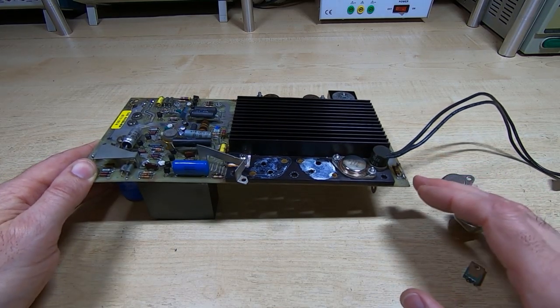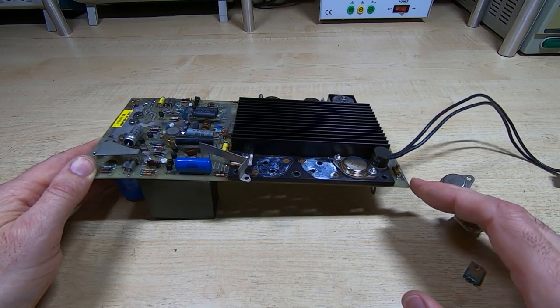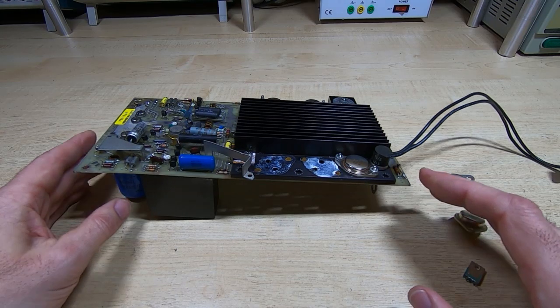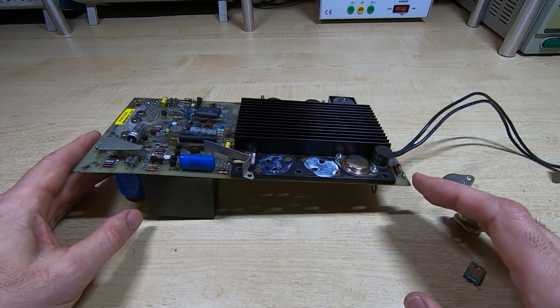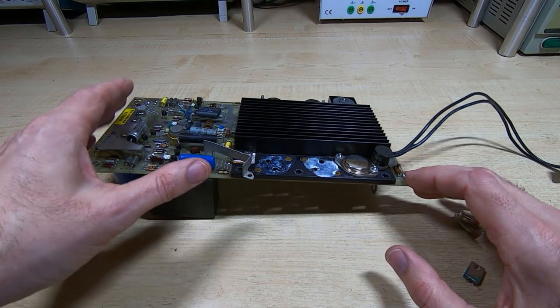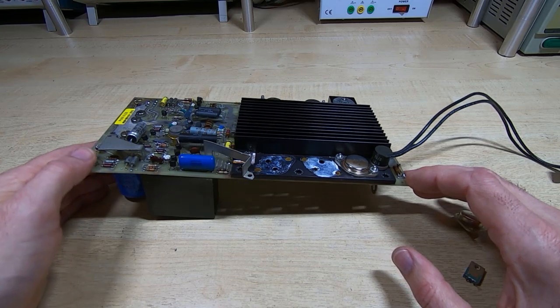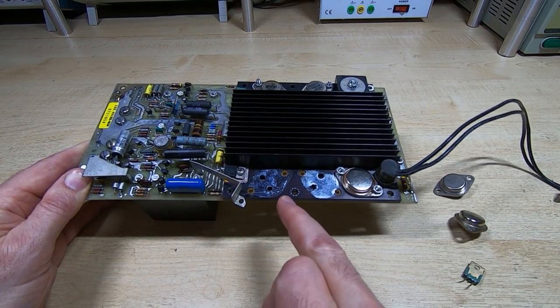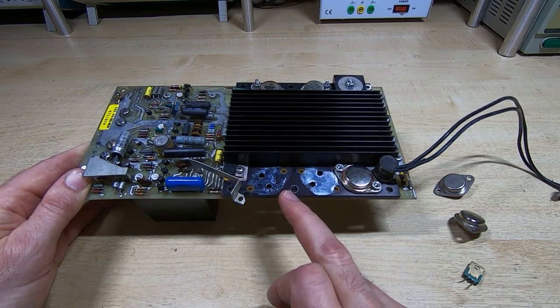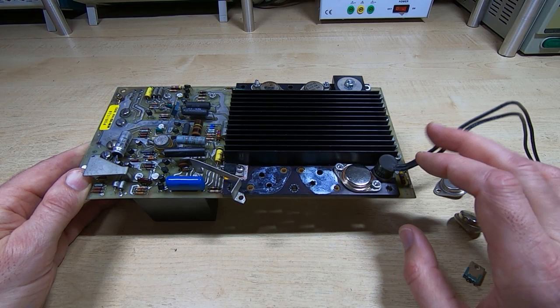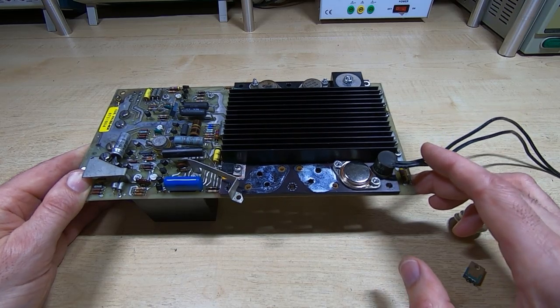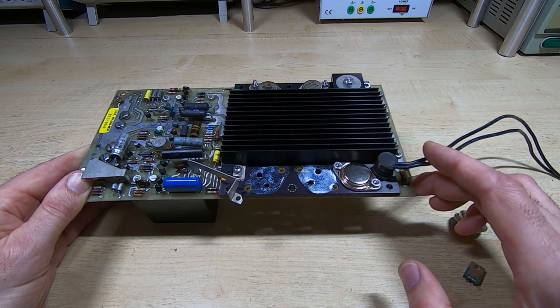I have a confession here that I fully expected it to fail, and in fact I expected it to fail a lot earlier than it did. I want to explain why that is. I had been through and tested all the major components as much as I could before we started the test. One of the things I found was the commutating diode from the plus 5V rail regulator was open circuit. So I was quite surprised that this thing was able to regulate the 5V rail at all, let alone in a fairly stable way.